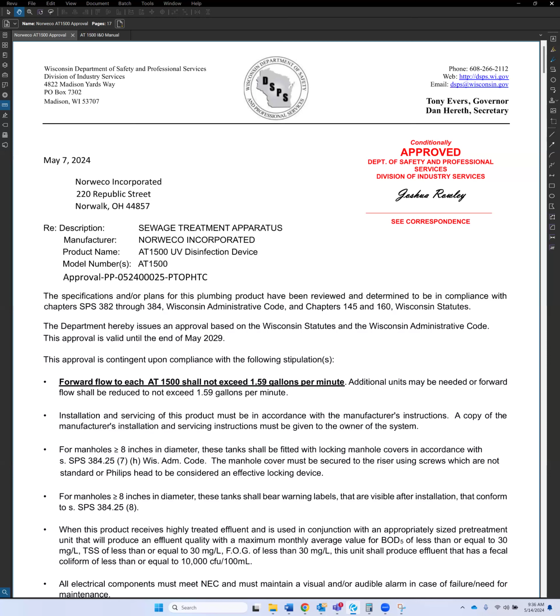It's going to depend on what their flow rates are and whether they're meeting that standard or not. So it'll be a case-by-case basis. And your annual sampling will show you if you're meeting the discharge standards or not. But ATUs are not granted approval for fecal reduction without disinfection. So there's just too many variabilities across the board and inconsistent results without having disinfection.